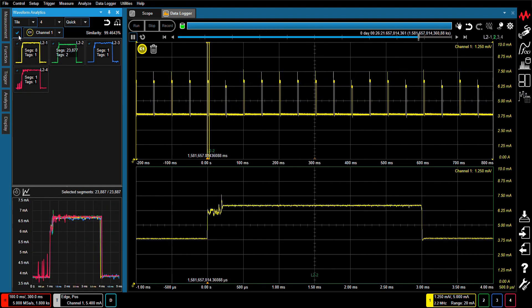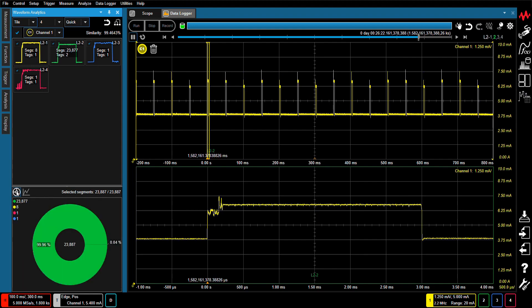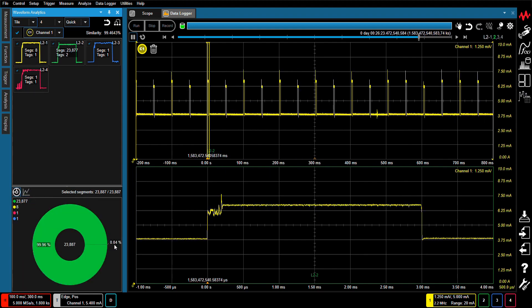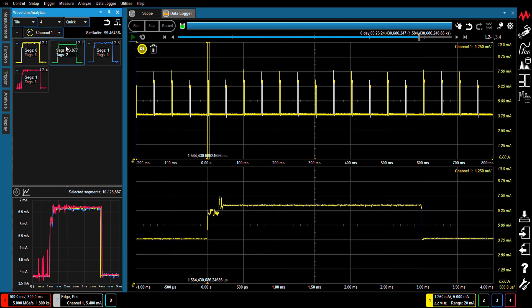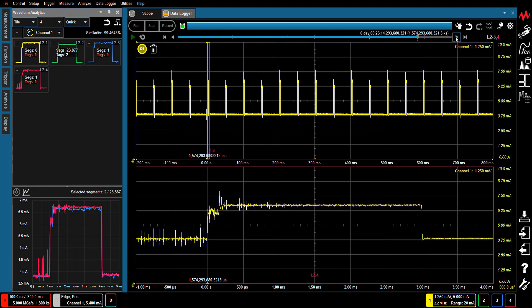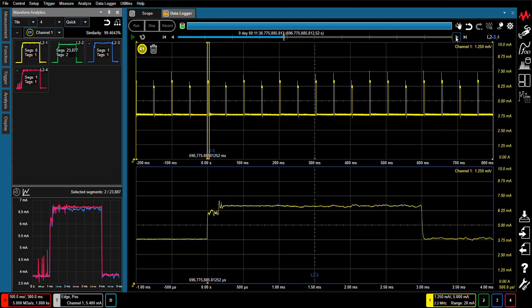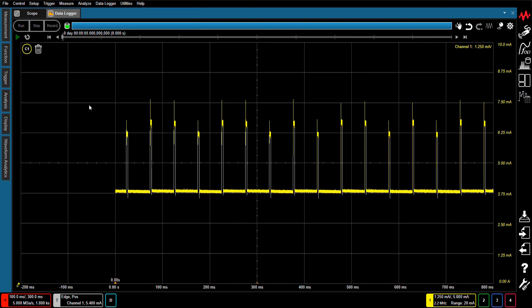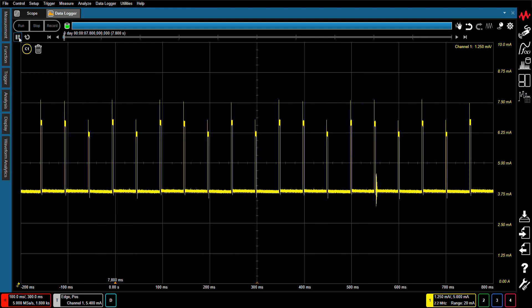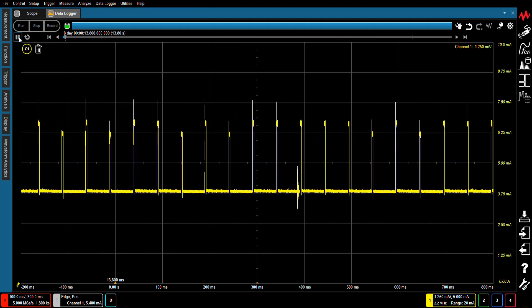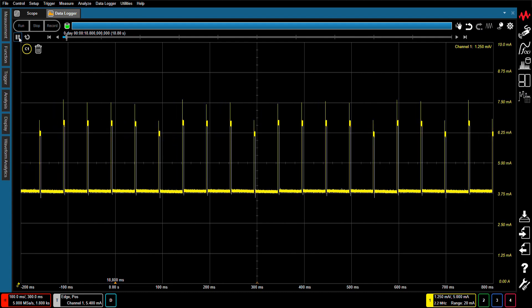Using machine learning techniques, the Anomalous Waveform Analytics feature can efficiently classify current and voltage waveforms in large waveform datasets of up to 100 hours duration. Now we are going to look at some actual measurement data to demonstrate failure analysis using the Anomalous Waveform Analytics feature.